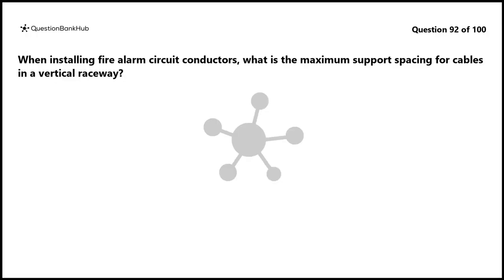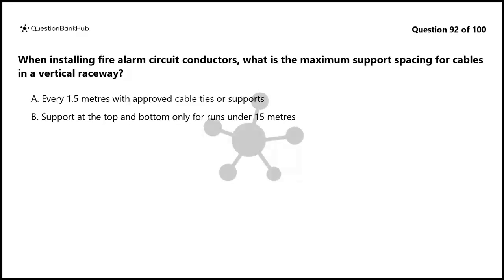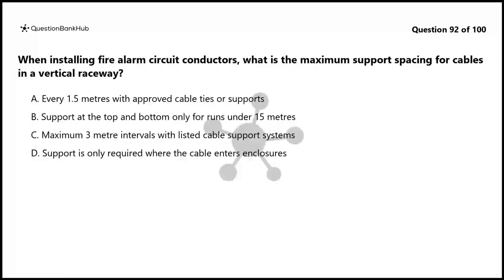Question 92. When installing fire alarm circuit conductors, what is the maximum support spacing for cables in a vertical raceway? A. Every 1.5 meters with approved cable ties or supports. B. Support at the top and bottom only for runs under 15 meters. C. Maximum 3-meter intervals with listed cable support systems. D. Support is only required where the cable enters enclosures.